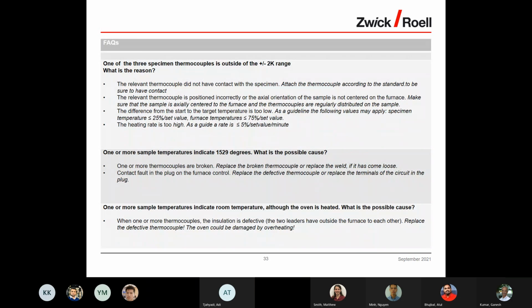Now we came to the FAQs. When one of the three specimen thermocouples is outside of the ±2K range, what is the reason? The relevant thermocouples did not have contact with the specimen. Attach the thermocouple according to the standard to be sure to have contact. The thermocouple is positioned incorrectly or the axial orientation of the sample is not centered on the furnace. Make sure that the sample is axially centered to the furnace and the thermocouples are regularly distributed on the sample.